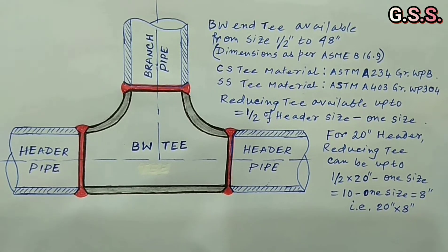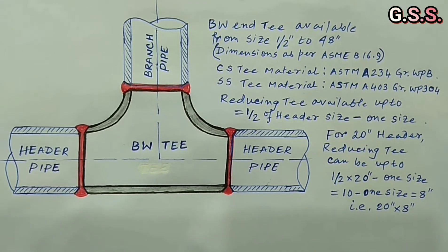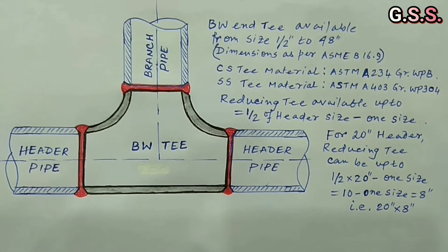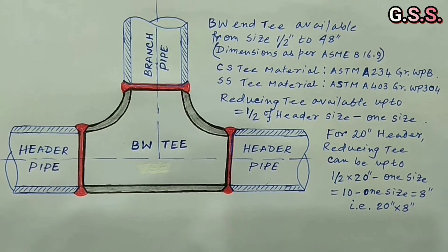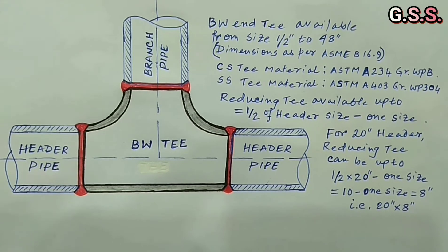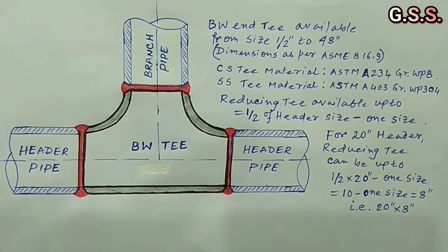Similarly for 4 inch header size, reducing T is possible up to 4 inch by 1 and half inch size. Similarly 48 inch by 22 inch reducing T is possible. Same philosophy is applicable for reducer also.